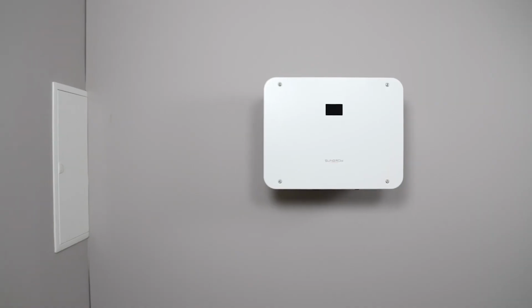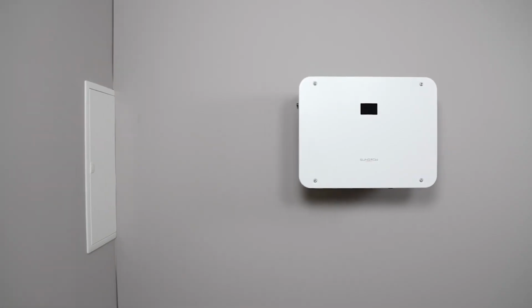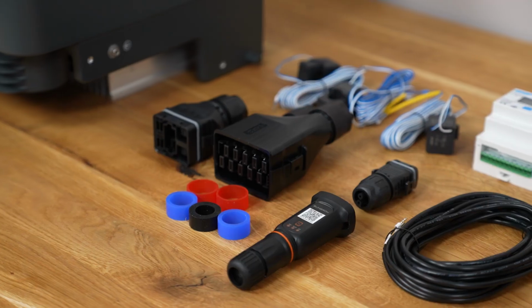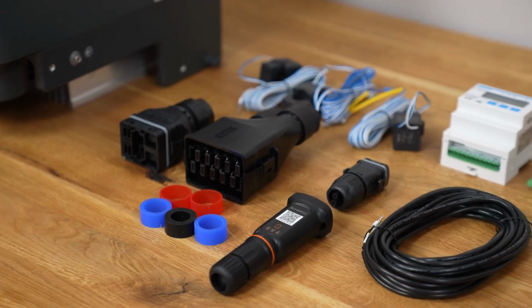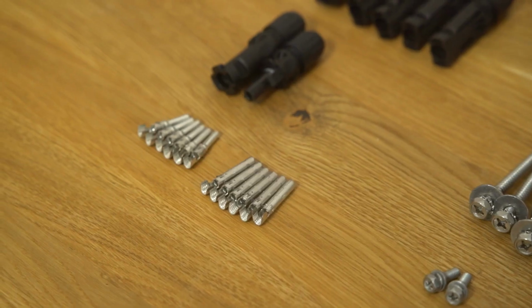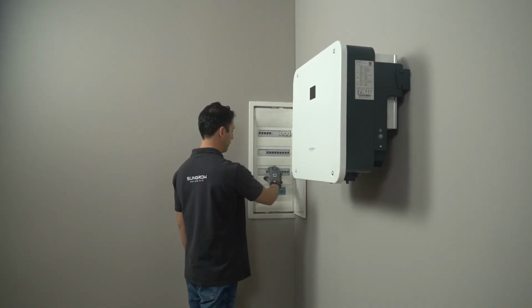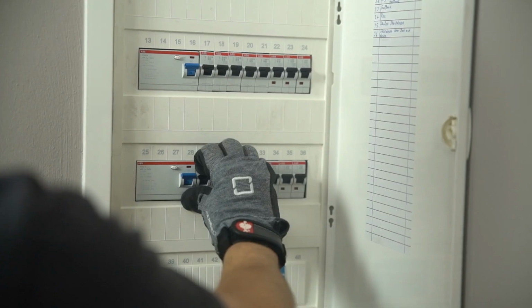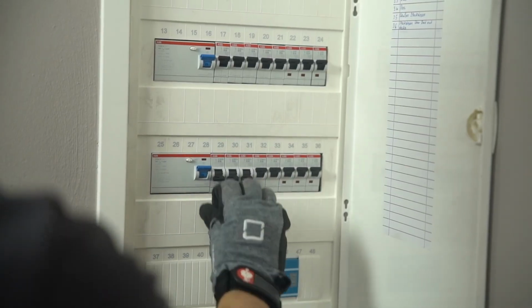Use the wall mounting bracket and the bottom mounting bracket to hang the inverter on the wall. All screws and plugs required for the installation are included in the delivery. You only need your own tools. And off you go! Before the inverter can be connected, the AC home circuit breaker must be disconnected.